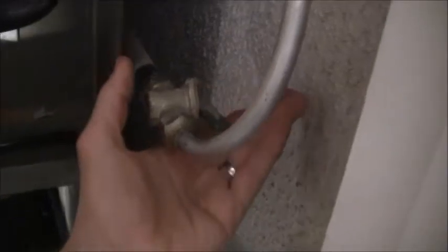I'm going to turn on the natural gas right here. Natural gas is now open. I'm going to take my lighter, see if it works. It does. And we're going to put it right there. All right, it actually lit right off. So we're going to let that heat up the thermocouple for at least 30 seconds. And then we want to turn on the thermostat to heat and get these burners fired off.